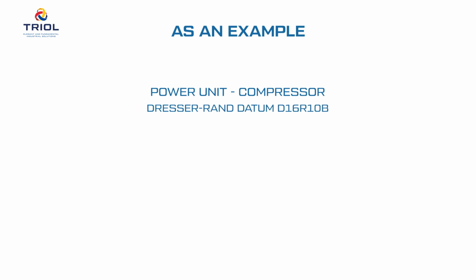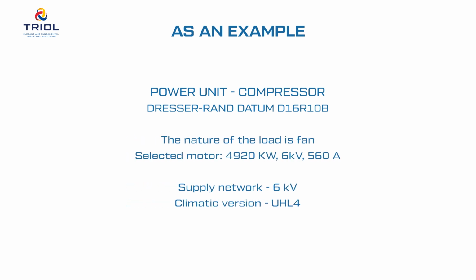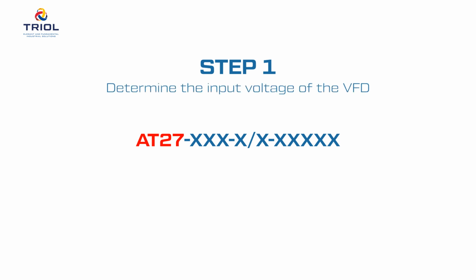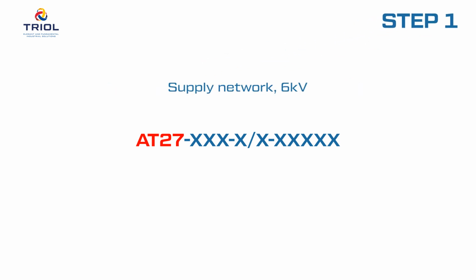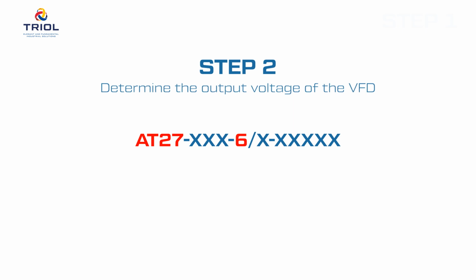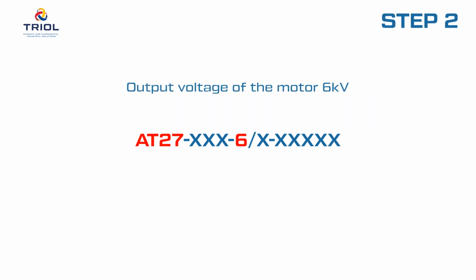As an example, consider a specific selection of a variable frequency drive for a power unit compressor, Dresser Rand Datum D16R10B, having the following parameters, working under the following conditions, with a set of required options shown on the screen. Step 1. Determine the input voltage of the VFD. Supply network 6000 volts is the supported standard of the supply main for AT27 and is coded in the designation with symbol 6. Step 2. Determine the output voltage of the VFD. The output voltage of the motor is 6000 volts, the motor voltage value falls within the standard Triol voltage range, and according to the voltage selection table, corresponds to the output voltage of the inverter with symbol 6.